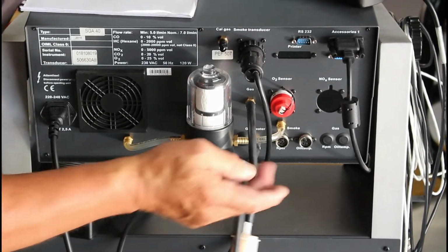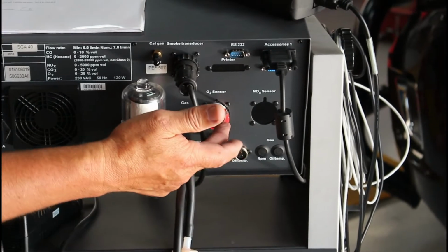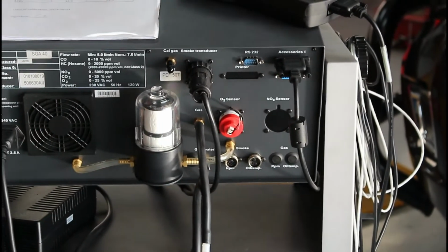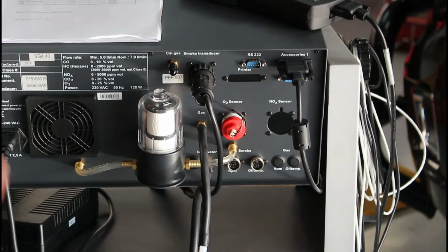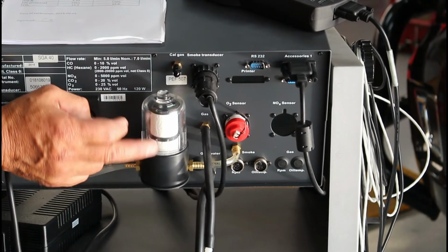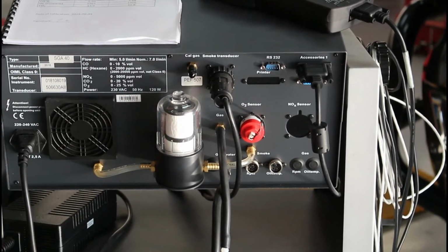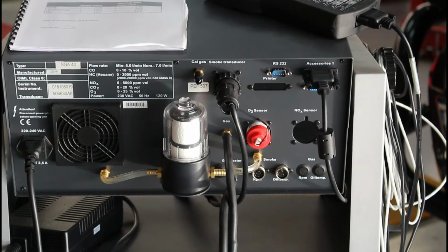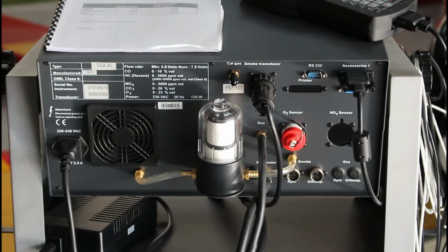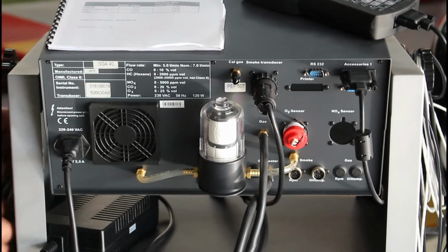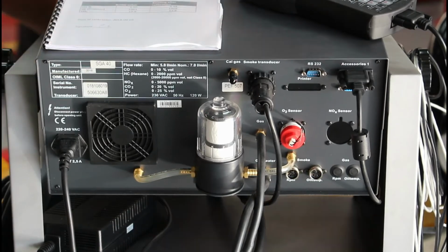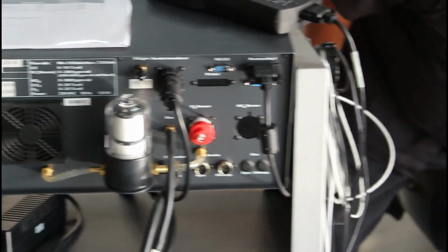So you've got your O2 sensor on the back there. Really, an O2 sensor has a shelf life and a time life, so you will have to change them and change the filters periodically. The machine will actually tell you when they're due to be changed. On the opposite side of this machine, we've got our opacity meter plugged in, which is through the front of the machine as well.